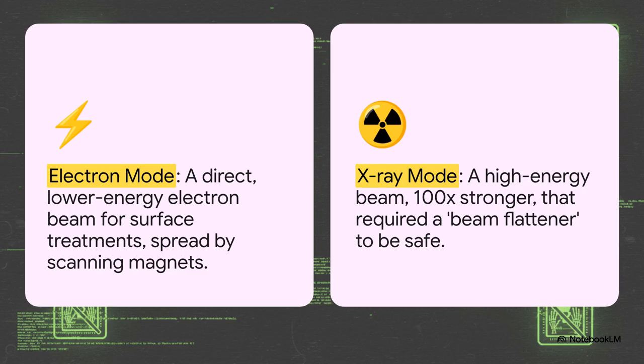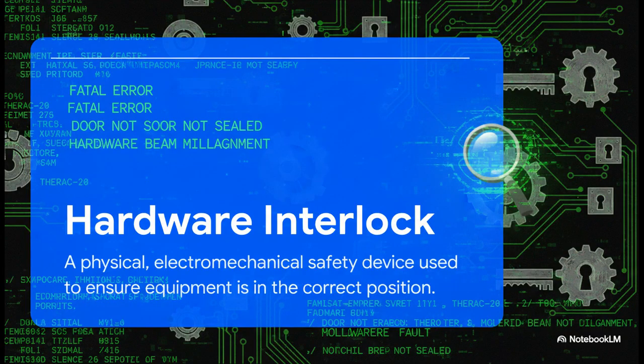But, and this is the important part, to be safe, that incredibly potent beam had to pass through a special shield called a beam flattener to spread out its energy. Now, on all the previous machines, like the Therac-6 and the Therac-20, safety was guaranteed by something called hardware interlocks. Just think of these as physical locks, a specific key that has to fit in a specific lock, a mechanical switch, a circuit that physically cannot turn on unless everything is in exactly the right place. They're simple, they're robust, and they are incredibly reliable.